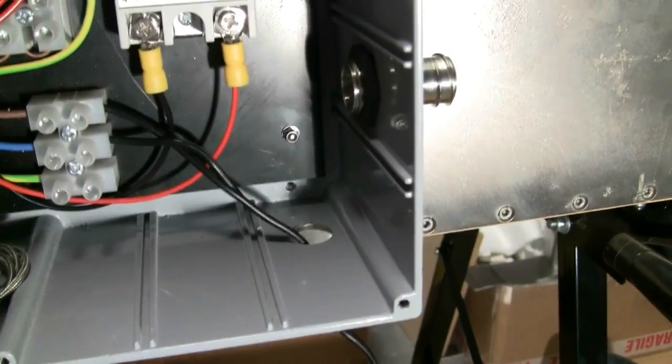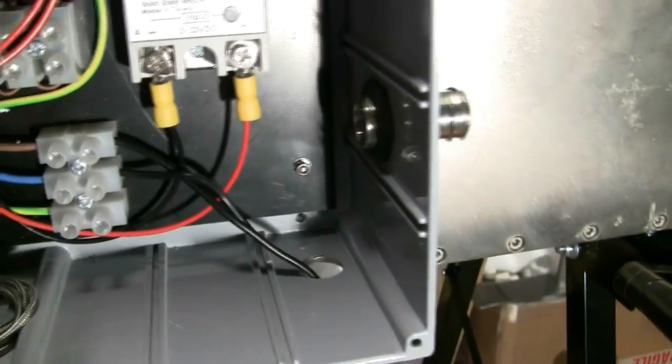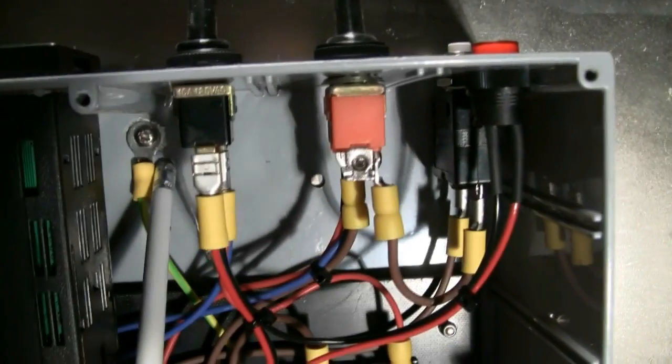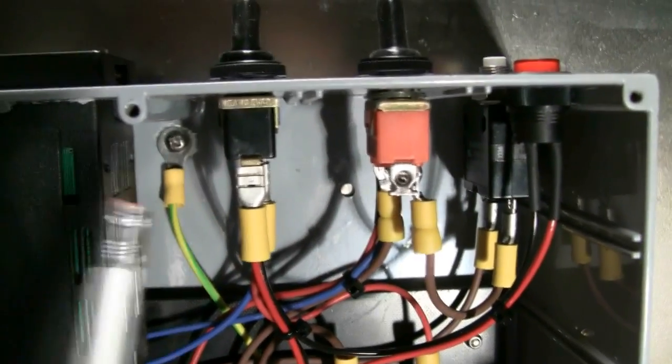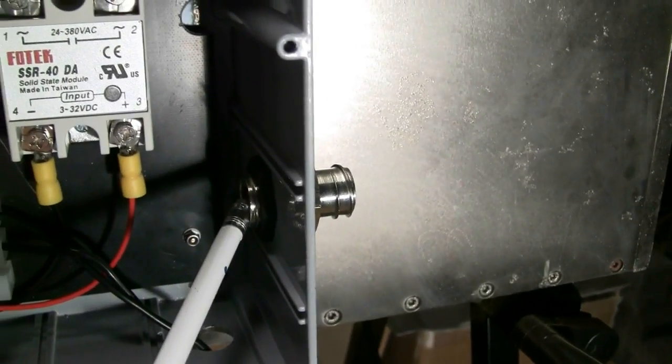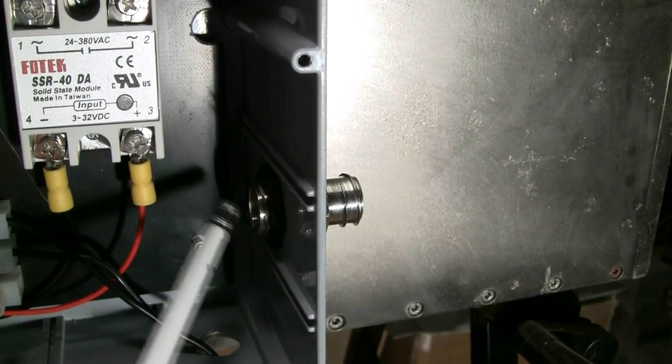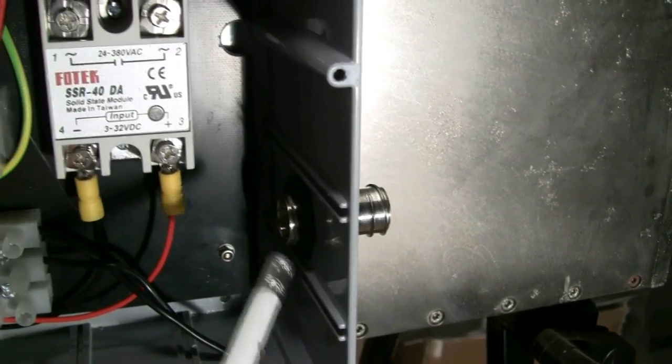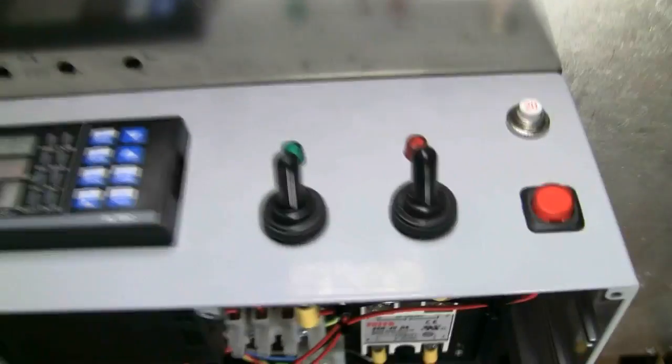We're good. There's earth through here, so this case is earthed and also this box is earthed. Then there'll be another earth which runs up through here which will earth the top lid. All good.